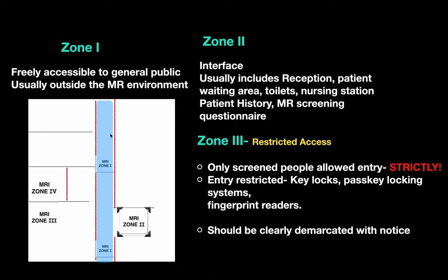Zone 1 is freely accessible to the general public, usually outside the MRI environment. Zone 2 includes the reception area, patient waiting area, toilet, nursing station, and is where patient history and MR screening are done. Zone 3 has restricted access — only screened people are allowed in, secured with a key lock system, pass key locking system, or fingerprint reader, and should be clearly marked with a notice.